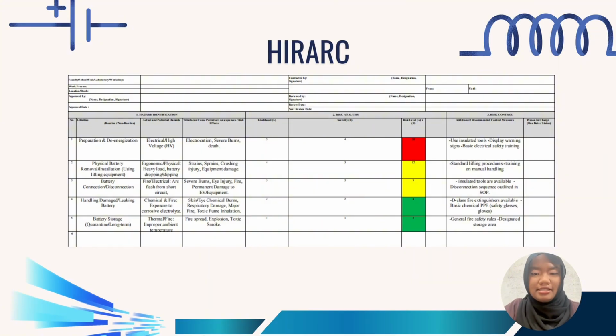The major hazards include electric shock, severe burns, fire risk, crushing injuries during lifting, chemical exposure from leaking electrolyte, and thermal-related fire hazard during storage. Based on our risk matrix, the highest risks come from high voltage work and lifting-related tasks, which fall into the red and yellow zones.